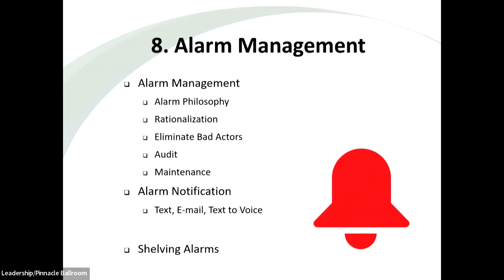To implement that, it's a bit of a process. You have to figure out what your philosophy is - what do you actually alarm on? Then you go through your alarms and figure out if this meets the philosophy. In that process, you eliminate the ones we call bad actors, the ones that keep popping up, sometimes unnecessarily.